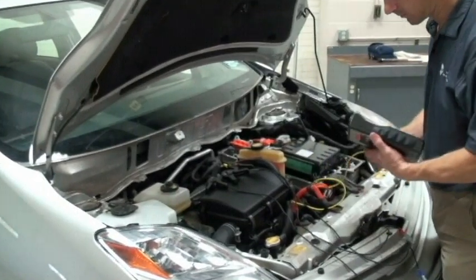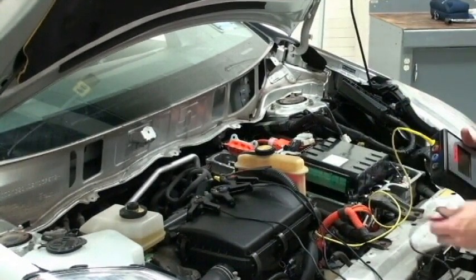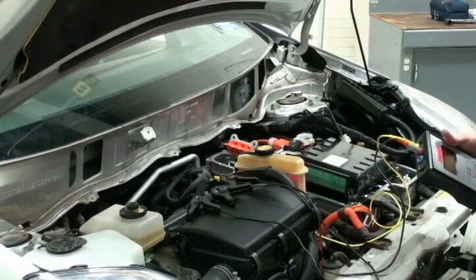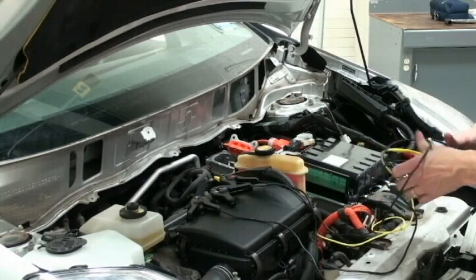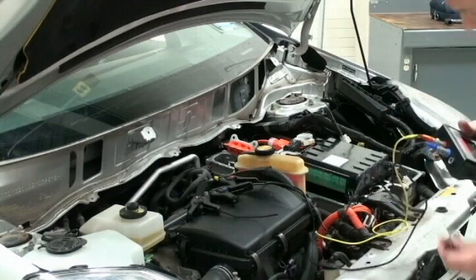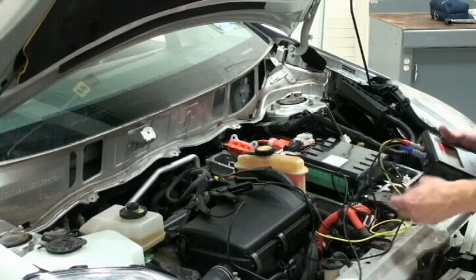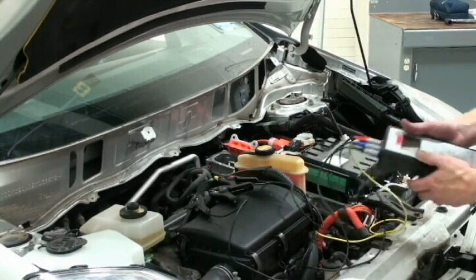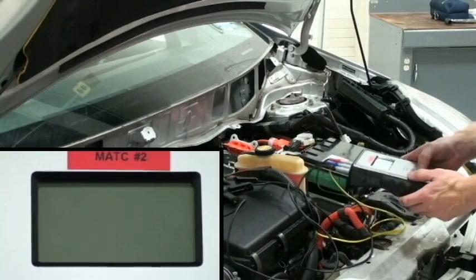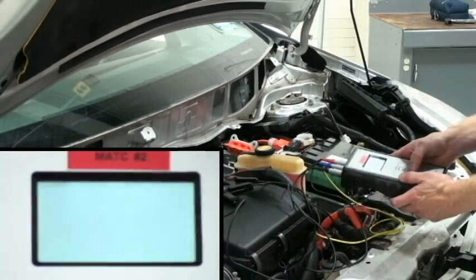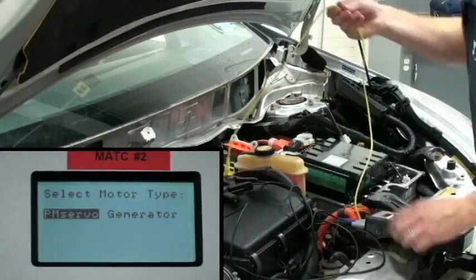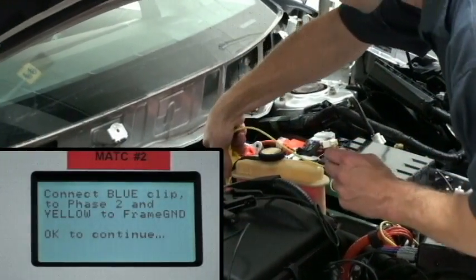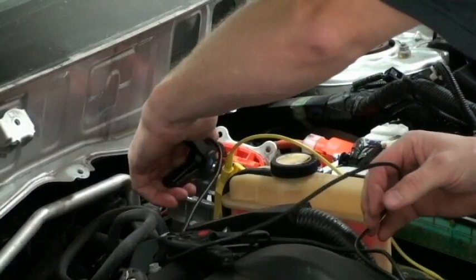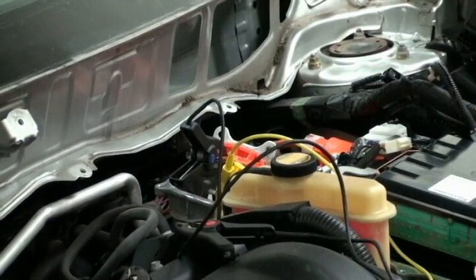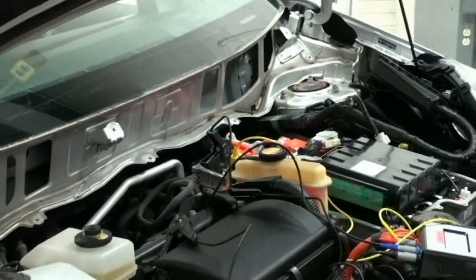Now it's time to begin performing the test with the AT33EV. The first test is going to be the dissipation factor and insulation resistance test. There are only two instrument test leads that are used for this test. The yellow clip, which is used for the insulation resistance test, which is hooked to chassis ground, and the blue lead, which is connected to the number 2 or center phase of the motor.